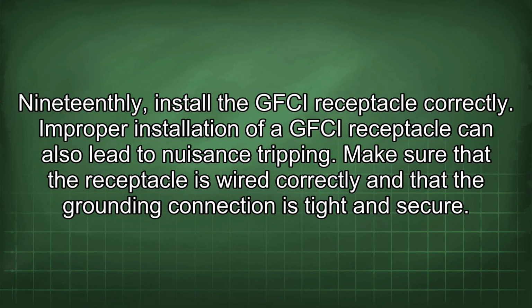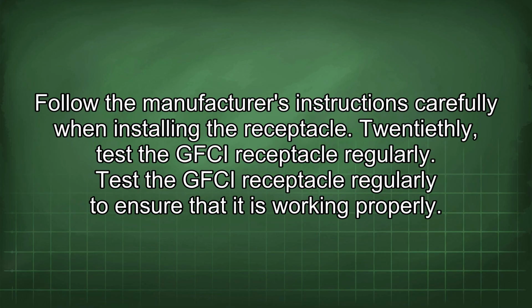19thly, install the GFCI receptacle correctly. Improper installation of a GFCI receptacle can also lead to nuisance tripping. Make sure that the receptacle is wired correctly and that the grounding connection is tight and secure. Follow the manufacturer's instructions carefully when installing the receptacle.